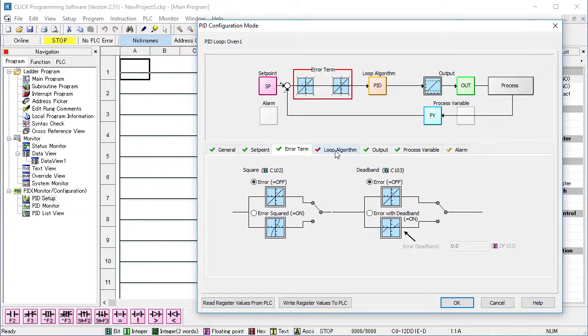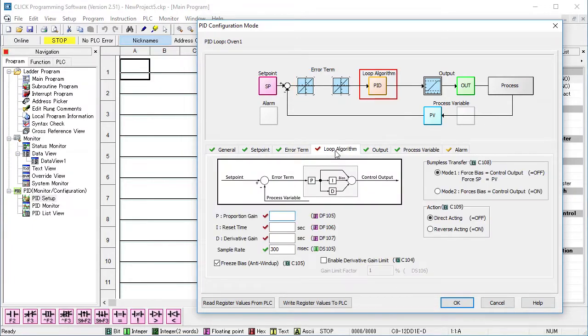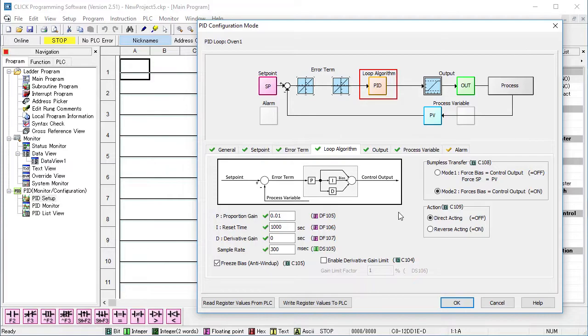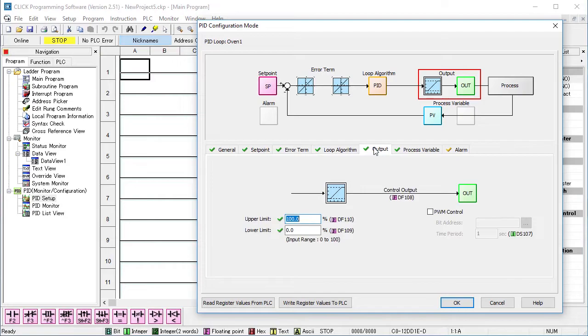In the loop algorithm section, we need to enter some starting values for the PID coefficients – the help file recommends these to prepare for auto-tune. We also have all the usual PID options. We do want to make sure Bumpless mode 2 is on to prepare for auto-tune. And we do have a direct acting system – green check mark, next tab.